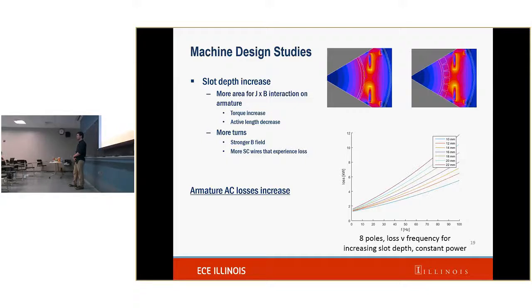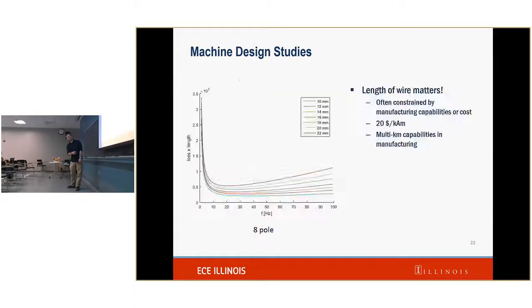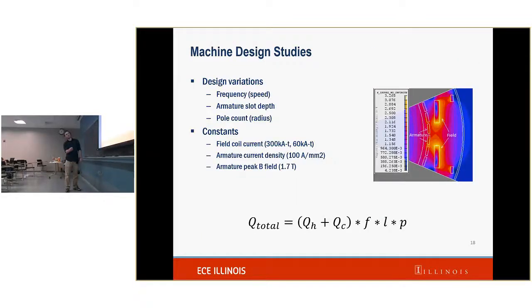So that 7.5 Tesla is a massive field. That's absolutely amazing. Is that why you guys are working on that extra external coil to dampen that out? Yeah. So you have your main field coil here, current going in here, current coming out here. You get your net field. And then we have our opposing field current going out there. So the net outside is going to be reduced while you're still keeping a very large margin in there. That was one of the main reasons for sticking with this design, because it solves the problem of the external field.